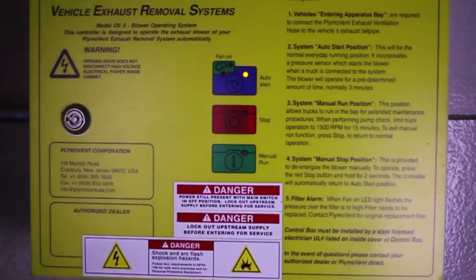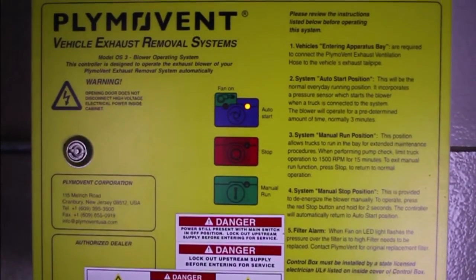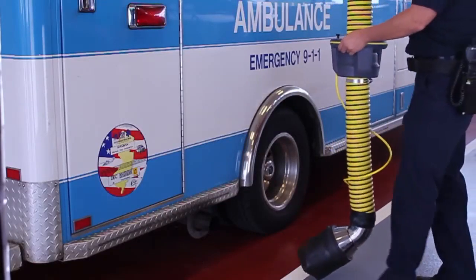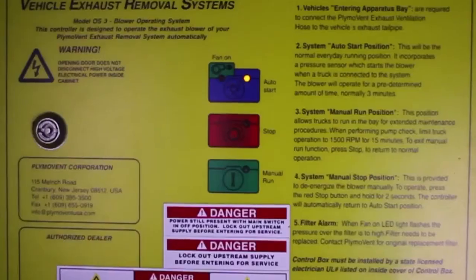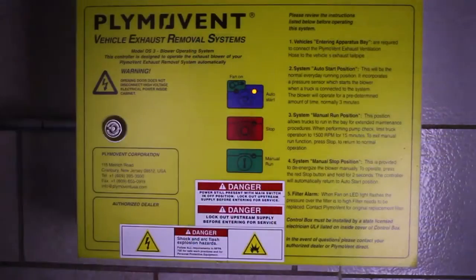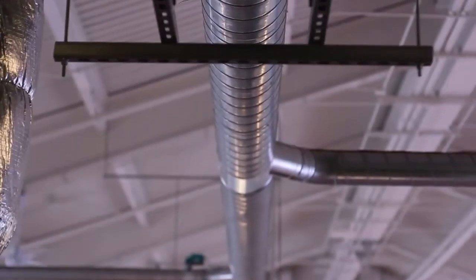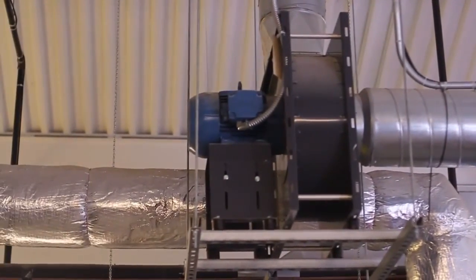The PlymoVent designed and manufactured control panel is UL listed, fulfilling all electrical codes for system operation. The auto-start system is based on static pressure when the apparatus is started. When the apparatus returns, a firefighter manually attaches the grabber nozzle to the tailpipe from the standing position — there is no bending over, as other systems do require. The exhaust system starts automatically as the grabber nears the tailpipe, sensing pressure and triggering the control panel and fan to engage. The control panel has a manual run feature for constant long-term use during vehicle checks. Be sure that your PlymoVent system is never attached to the apparatus while it is going through the regeneration process; regeneration should be done in a safe area outside the station. The PlymoVent spark-resistant fans are built specifically to meet Class II conveying of hazardous material requirements and are AMCA certified.